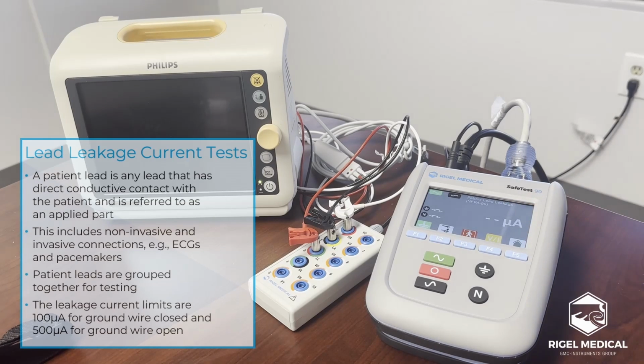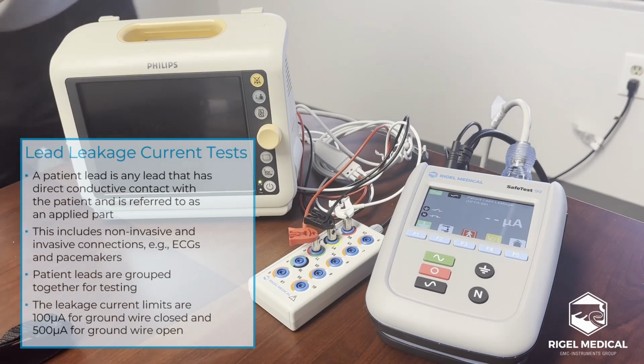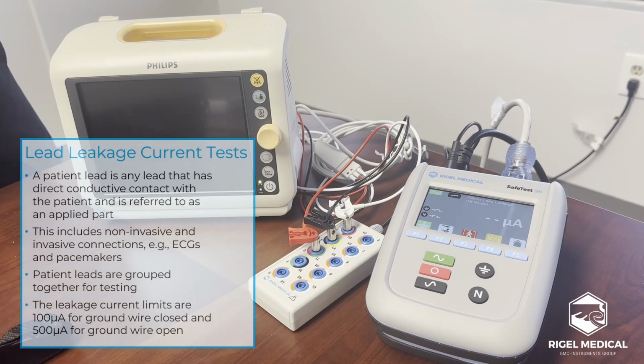And if I now scroll down to the next slide, we've got lead leakage current tests. So that's for all leads that are in direct conductive contact with the patient and is referred to as an applied part. So we've got 2 different leakage current limits here. 100 microamps for ground wire closed and 500 microamps for ground wire open.